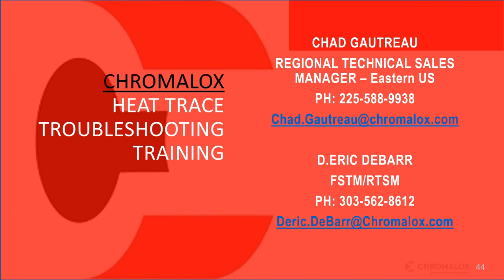Okay. And this next question, it's a good question, and maybe the photo we showed didn't illustrate what was going on there. Would it not be better to put the RTD in the shade, so it is reading the worst case scenario, especially if some heat trace piping is in shaded areas? No, because what we're trying to do is sense ambient temperature, and if the RTD is in the shade and it's cold outside, then we're not going to get the proper reading. We want it to be exposed to the sun so that we know what the true ambient is. And even though we have piping that's in shade, it's heat traced and insulated, so that's not really going to affect anything once the heat tracing's turned on.